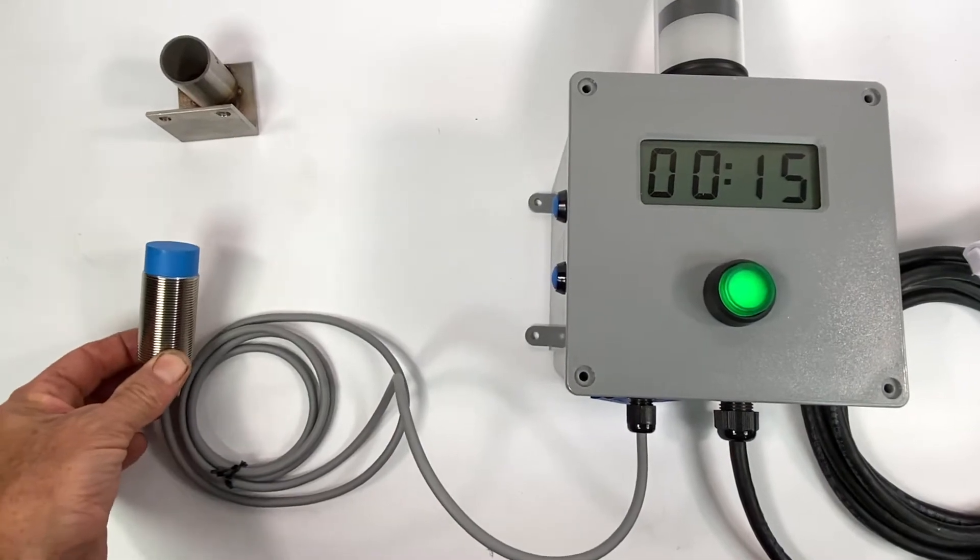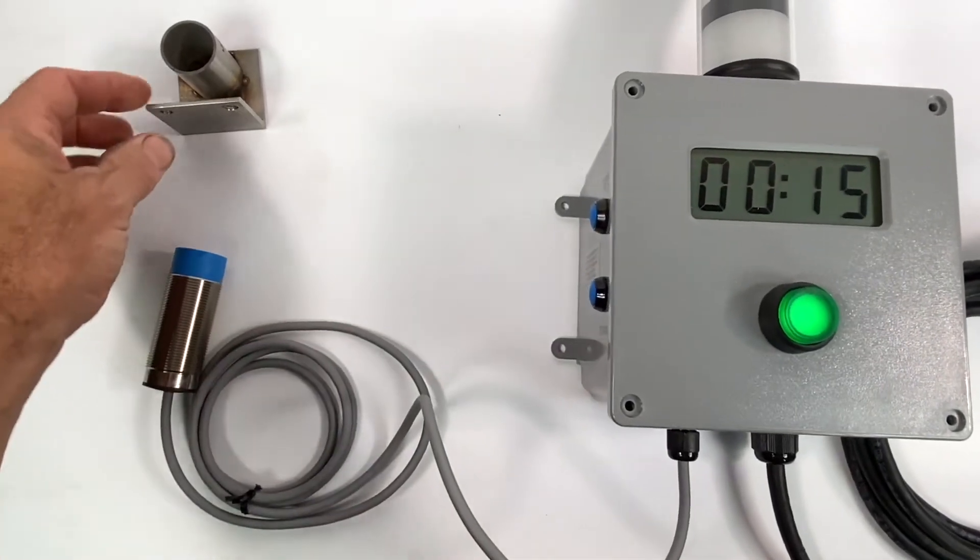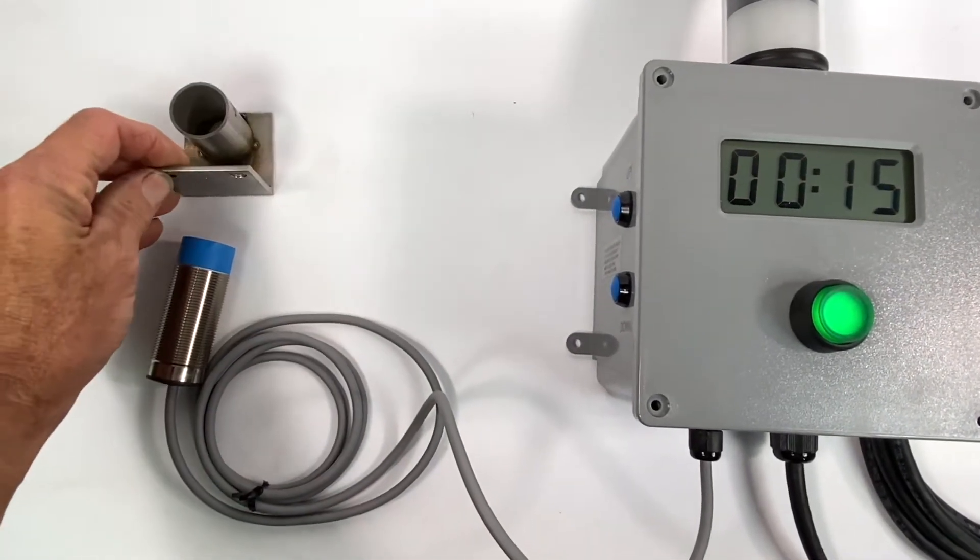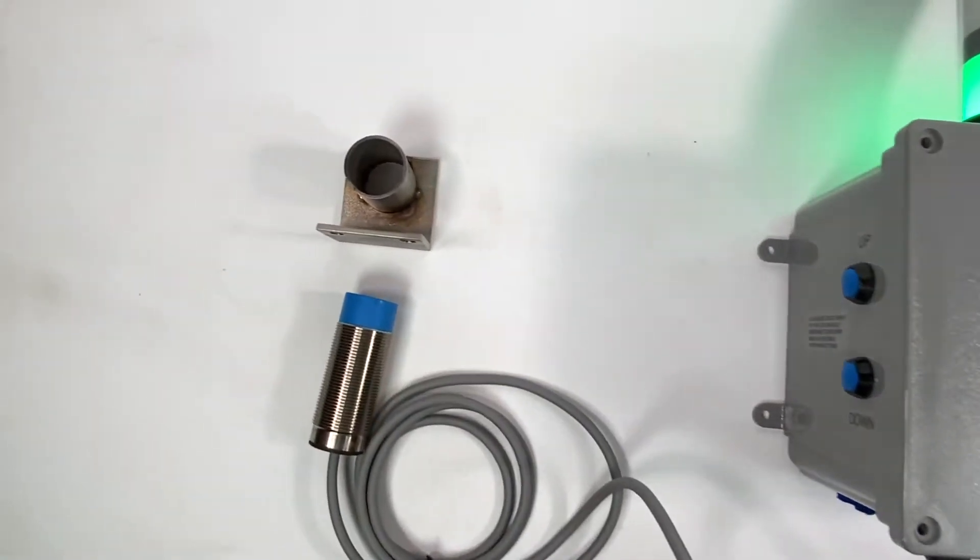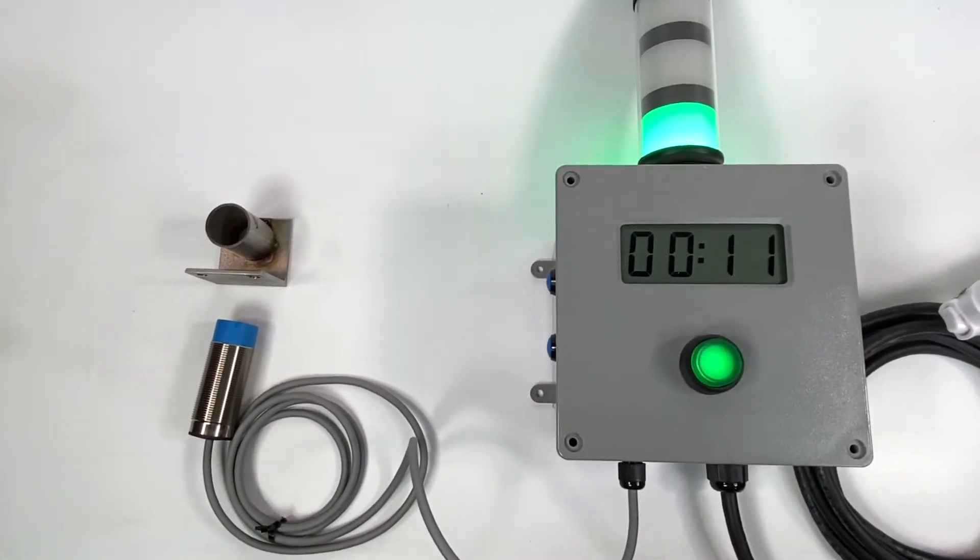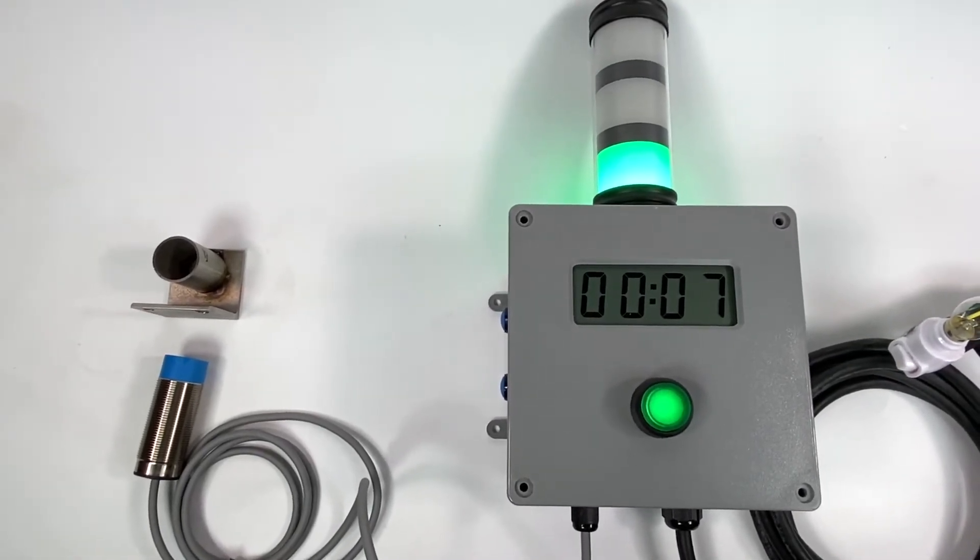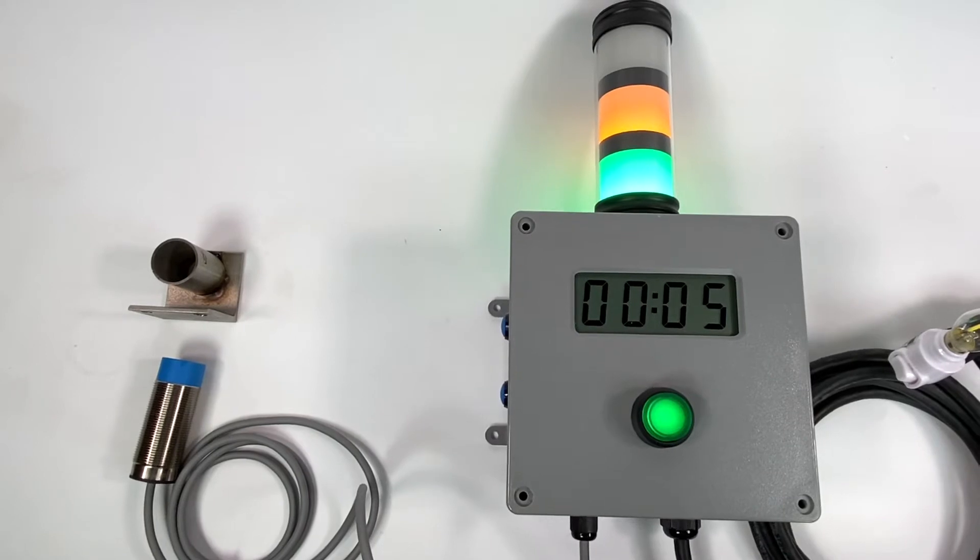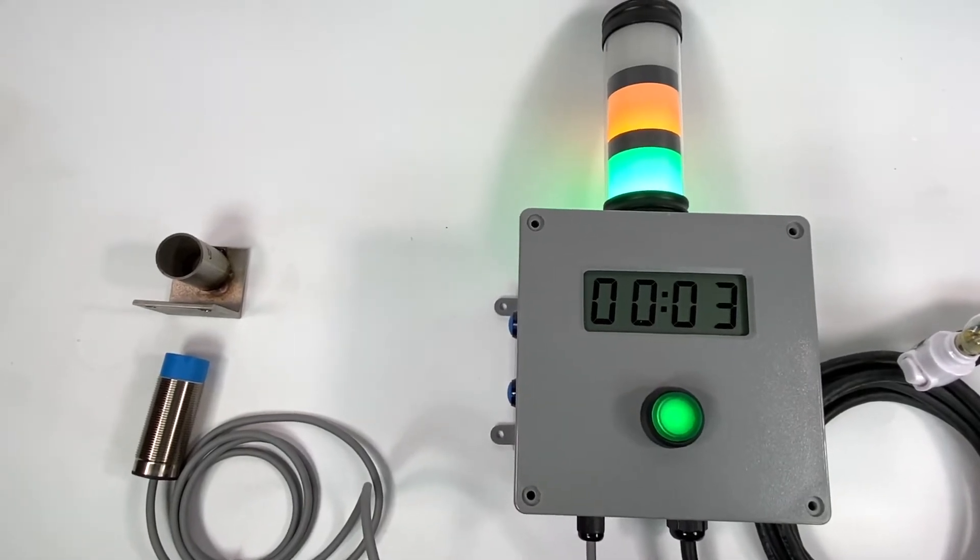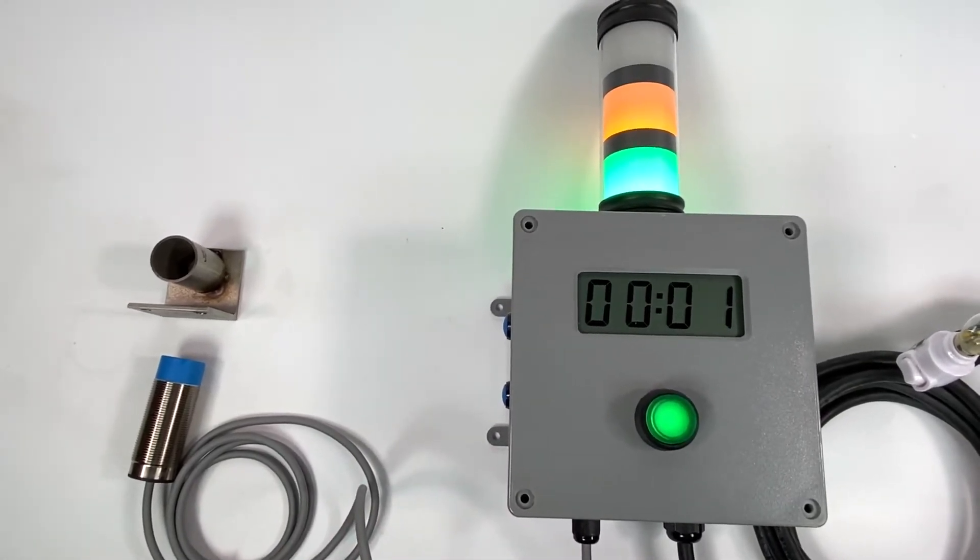This is an inductive proximity switch. In this case it's sensing a stainless steel bracket, and you can see that it's quite some distance away, 40 millimeters away, and it'll initiate the cycle. There's an early warning right there that calls the operator over to tell them that the end of the cycle is close.